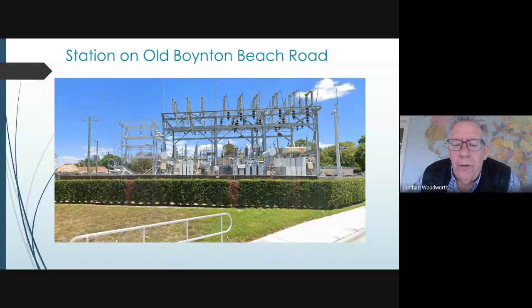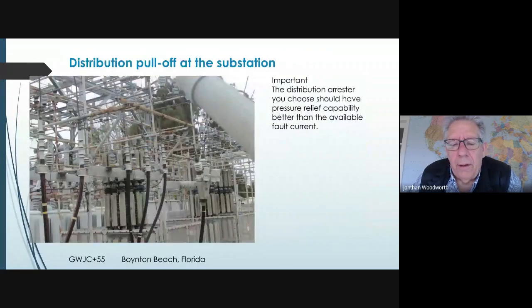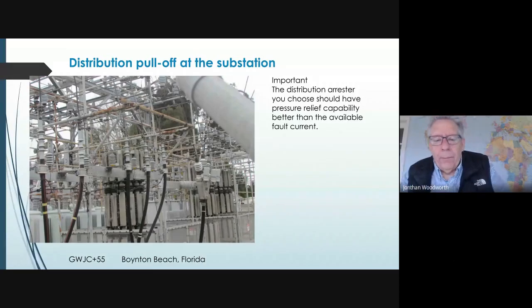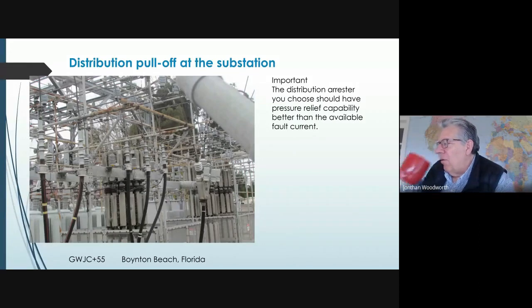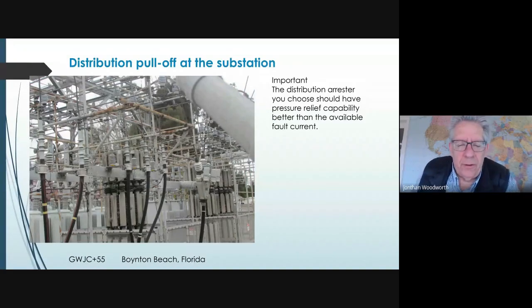Here's a high voltage substation in Florida. These are quite compact. When you get into urban areas, things are really tight. It's very confusing as to what wire goes where. But the solution to this is called GIS. And what we're seeing pop up around the world are gas insulated substations. A gas insulated substation is very small in size, because instead of using air as the insulation, it uses SF6, and it's all enclosed in metal housings, and it can be used in urban areas.